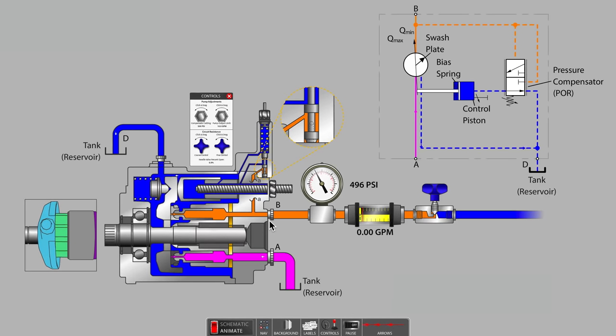The pressure compensated pump is also referred to as a variable displacement pump. When there is no flow path, as is the case with our closed needle valve, the pump simply destrokes itself to produce near zero flow.